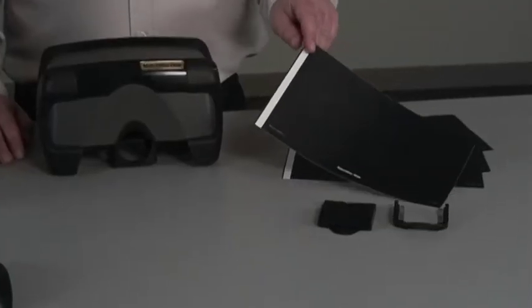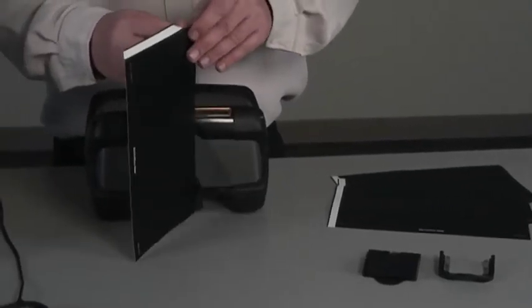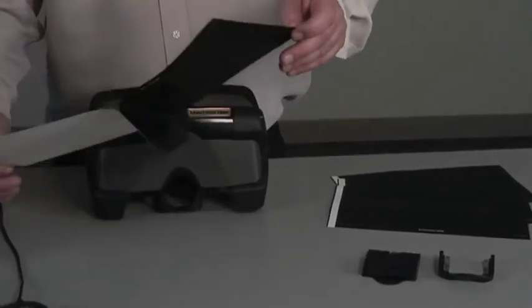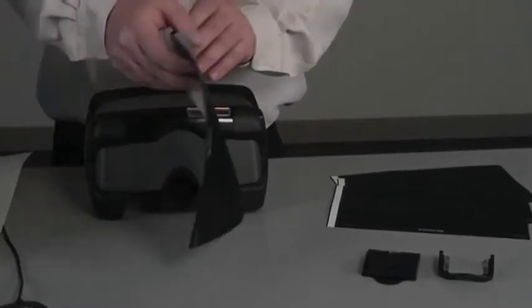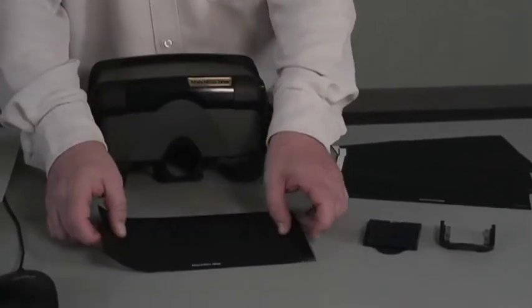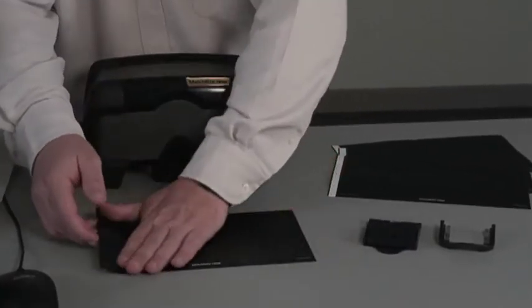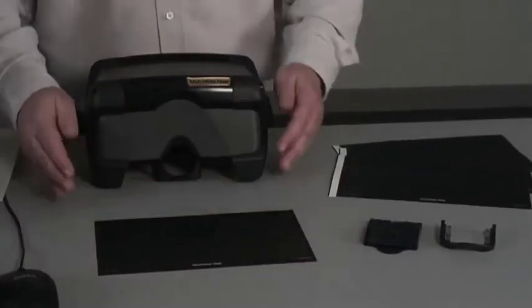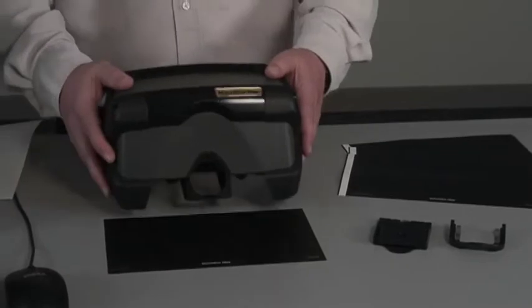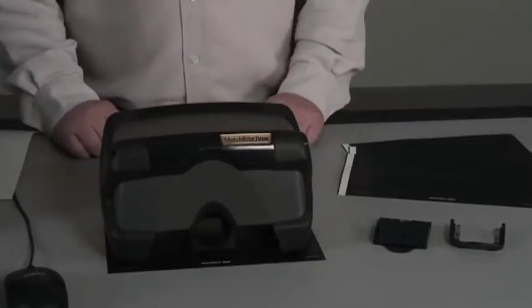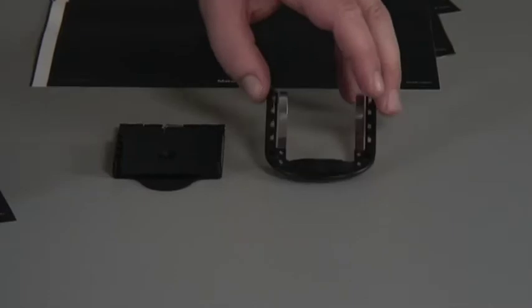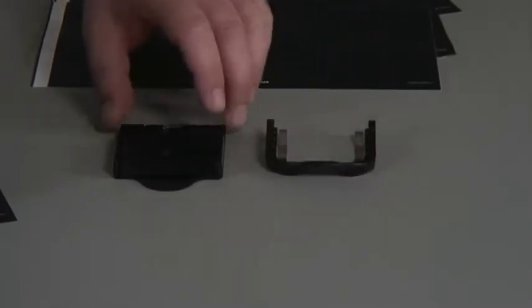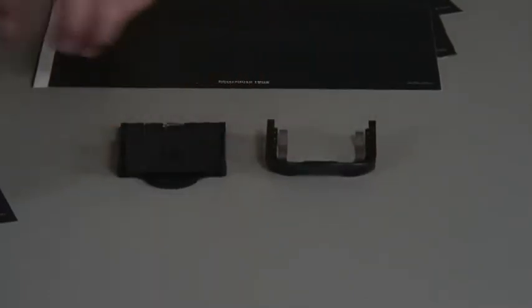While that's powered up, let's look at some of the accessories. It's important to take the self adhesive black mat and place it in a position where most of your color measurements will be taken. One of the things we don't want is light reflecting off of the countertop while doing a measurement. The other accessories, the sample holder and the chip clip, will allow us proper sampling for when we do custom matches.